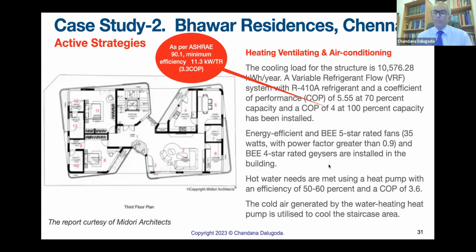Now, to achieve energy saving and comply with green building requirements, the ASHRAE 90.1 energy efficiency standard gives the minimum efficiency we should have for VRF systems. As per ASHRAE 90.1, efficiency should be 11.3 kilowatt per ton, or in COP, 3.3.